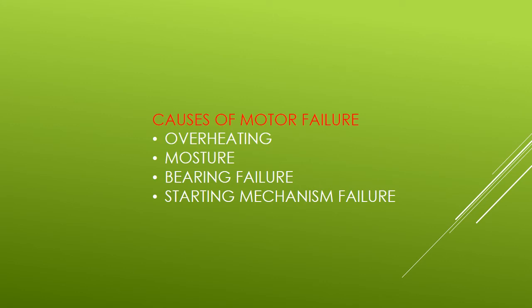Overheating. Heat is one of the most destructive agents and can cause premature motor failure. Overheating occurs because of motor overloading, low voltage at the motor terminals, excessive ambient temperatures, or poor cooling caused by accumulation of dirt or lack of ventilation. If heat is not dissipated, insulation failure can result, ruining the motor.